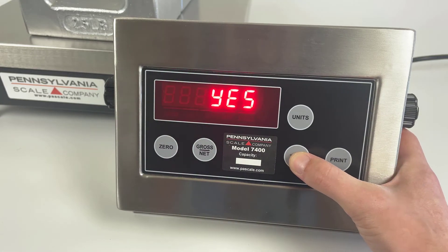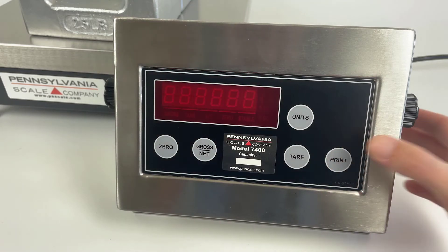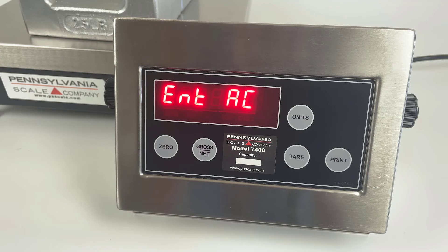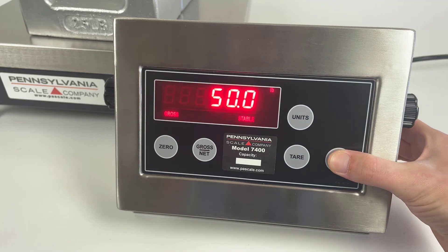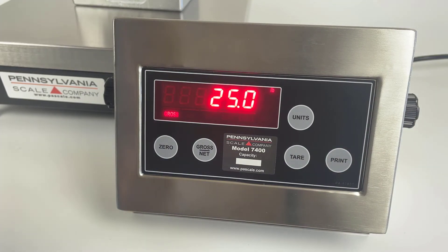Press print again to see the save screen. The tare key changes the 'no' to a 'yes', and then print confirms. The ENT AC screen allows you to change the access code, or you can press the print key to return to weighing mode.